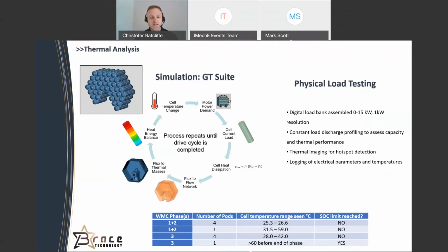And the table below, you can see the findings from that. In the top line, we have the one and two phases that we talked about, utilizing four pods joined together - so we're not loading one pod, we're taking it from the four pods together. We can see there's no state of charge limit reached, so the pods don't deplete, and the cell temperatures remain relatively low, just above ambient.